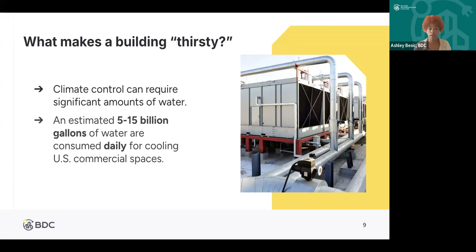So what actually makes a commercial building thirsty? Many commercial buildings use a combination of chillers and cooling towers. Chillers use refrigerant to absorb heat, and the cooling tower consumes, evaporates, and discharges water to release that heat, meaning that just by working perfectly, cooling towers are designed to consume tons of water. An estimated 5 to 15 billion gallons of fresh water are consumed daily for cooling commercial spaces in the US. On top of that, the water needs to be chemically treated to prevent pathogens, adding additional operating costs and risk to cooling buildings.